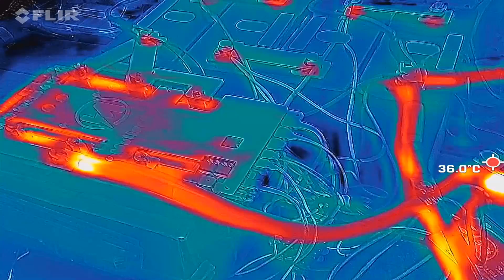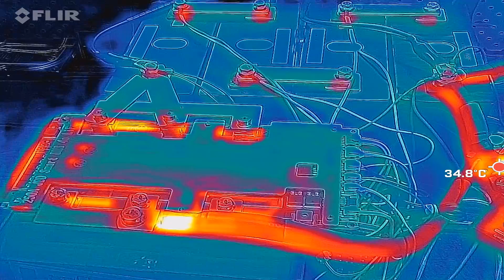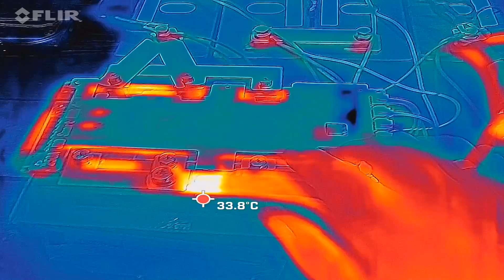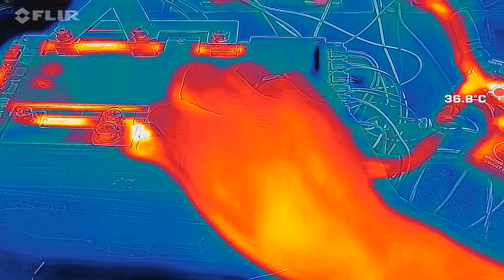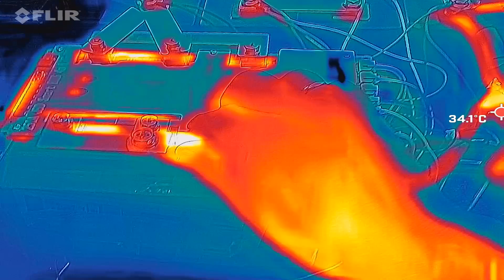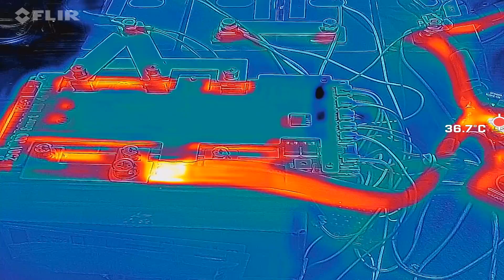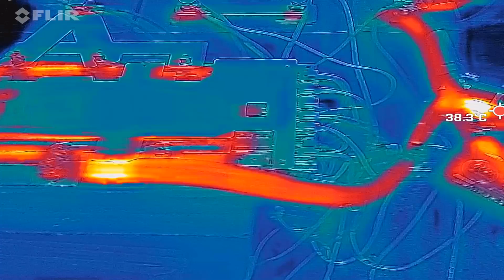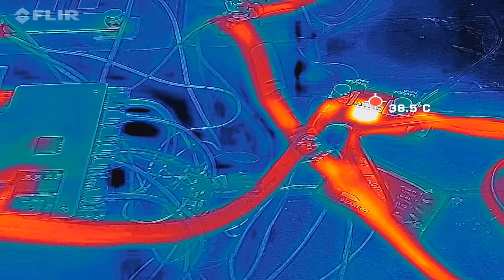Okay, we are now having a look at the battery situation at 206 amps. You can see the terminals heating up a little bit on the battery, and in the foreground is the BMS. We have 33 degrees on the outgoing terminal, but this could be more like a crimping issue here, I guess, from the 70mm cable. This is actually the off-cut cable I used, which we cut off our Phoenix inverter when we installed the transfer switch.